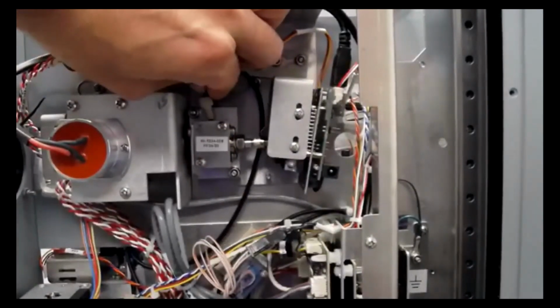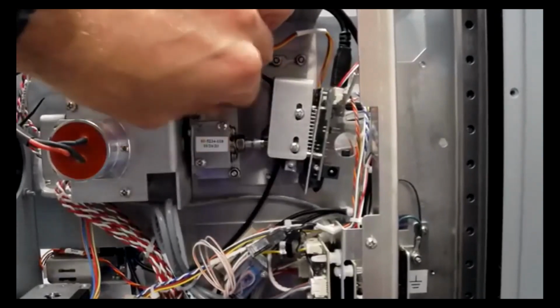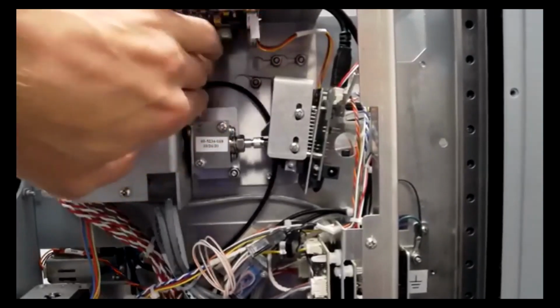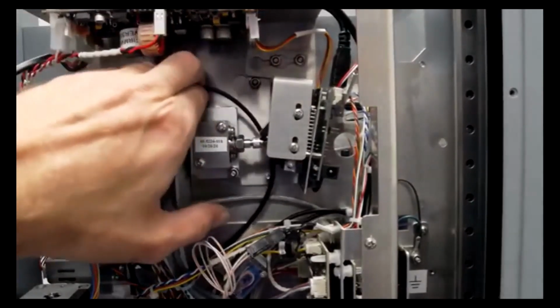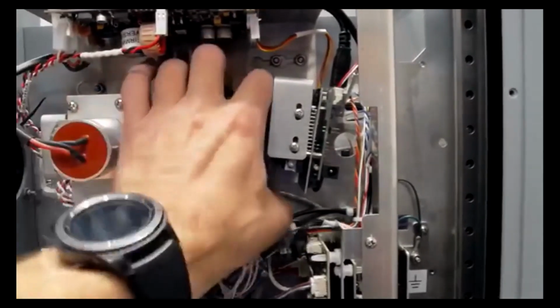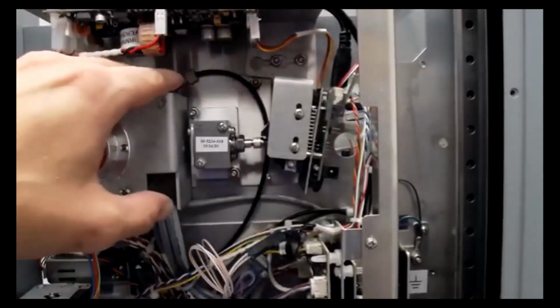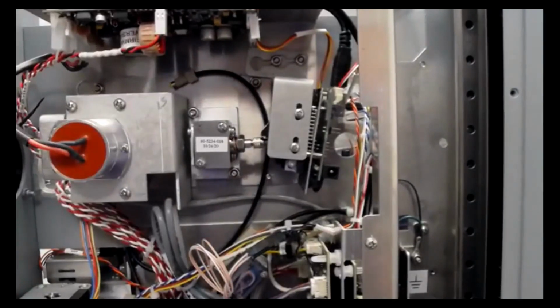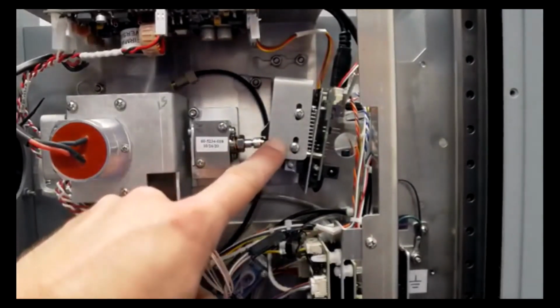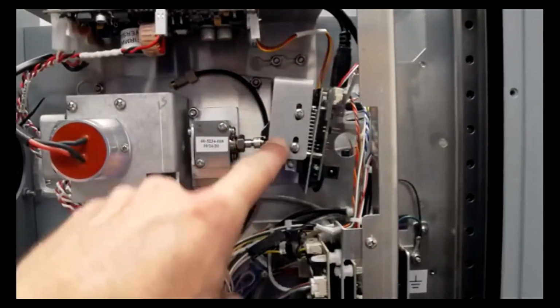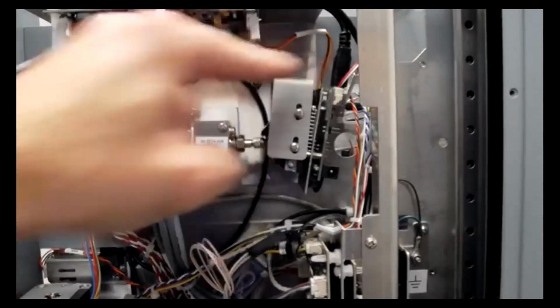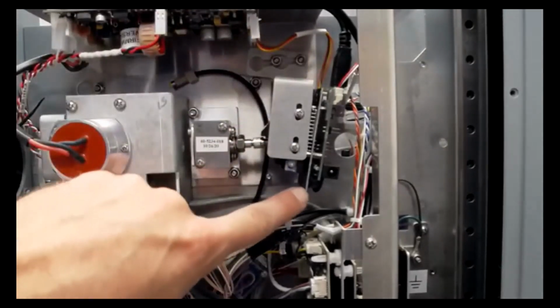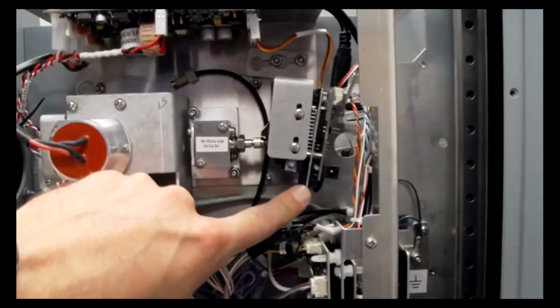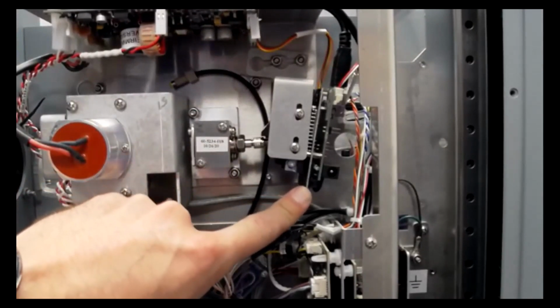Might have to wiggle it a little bit, as sometimes that ferrule can get stuck on threads. You can just leave that tubing wherever you need to, so long as it's out of the way. Now we need to move the detector, okay? There's going to be a nut here and here that we need to remove, and this is the configuration 2 detector. You might have a configuration 1.